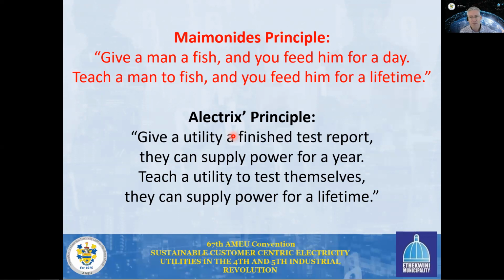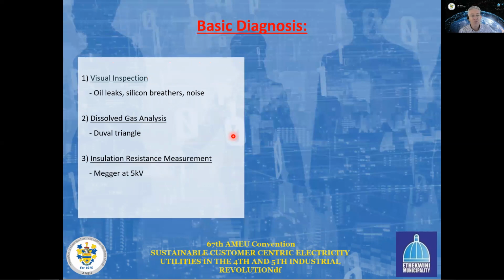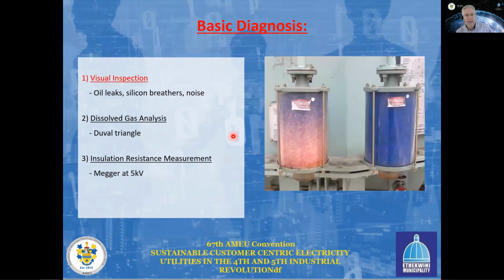And this is really the purpose of my presentation here today: to provide you, the municipalities, with a toolbox of the tests that can be done on a power transformer, so that you can provide power to your customers for a lifetime. I've categorized this into 3 categories. Firstly, the basic tests that can be done on a power transformer, which is number 1, just basic visual inspection of a power transformer, looking at the transformer, recording oil leaks, looking at the silicon breathers, recording any funny noises coming from the transformers.